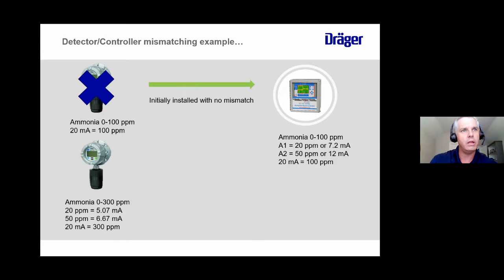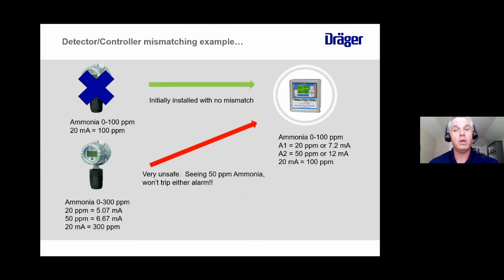So guess what? Now when the transmitter sees 20 ppm, for that range of 0 to 300, it's only going to send out 5.07 milliamps. If it gets to A2, 50 ppm, it's only going to send out 6.67 milliamps. Guess what, guys? That controller at those milliamp values is not even going to set the A1 alarm off. That's a very unsafe situation.